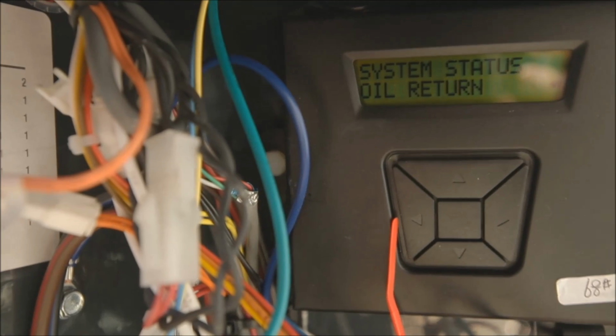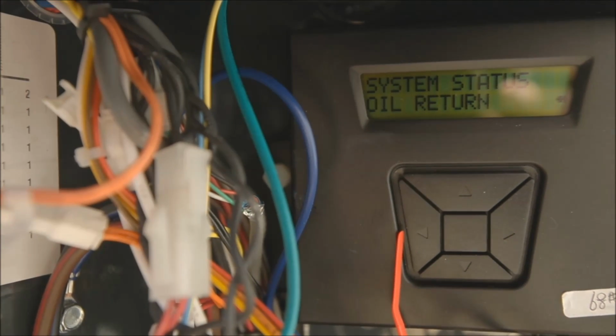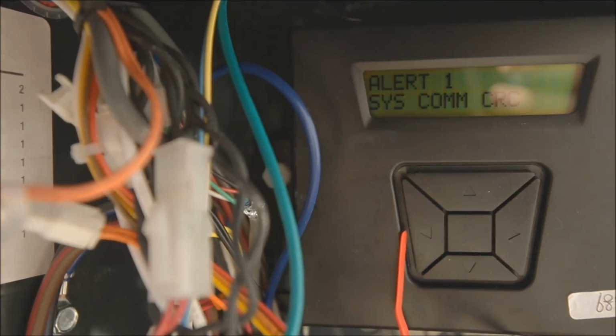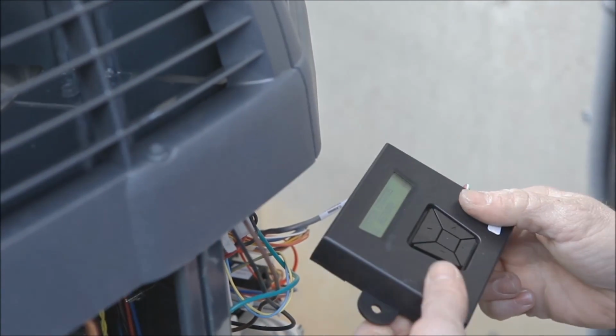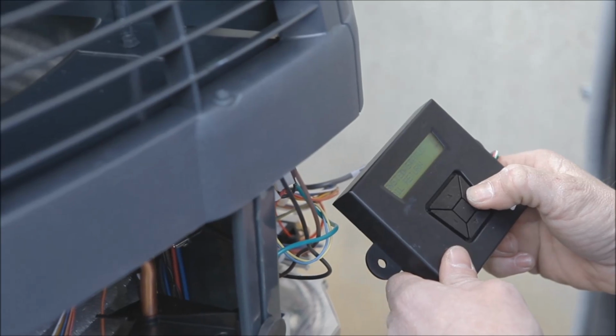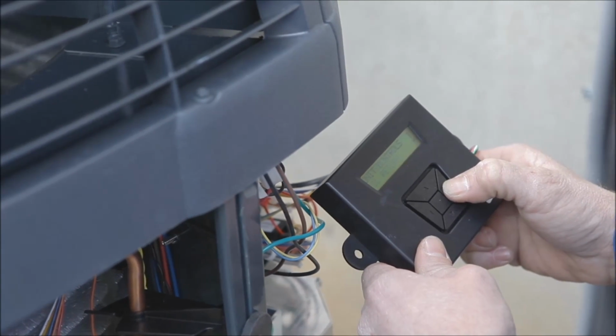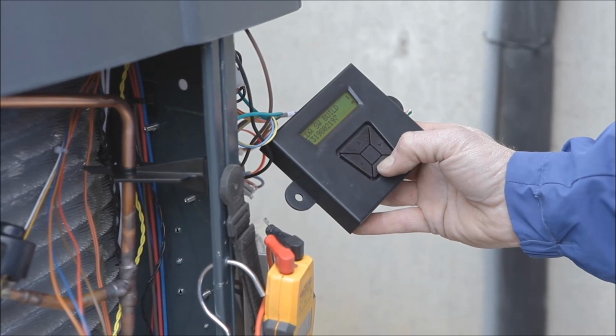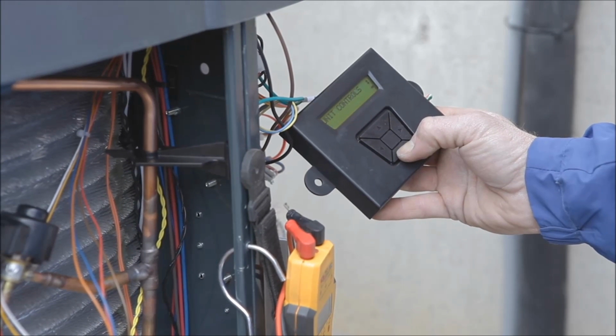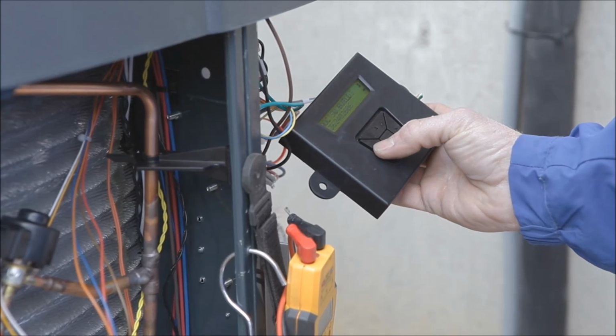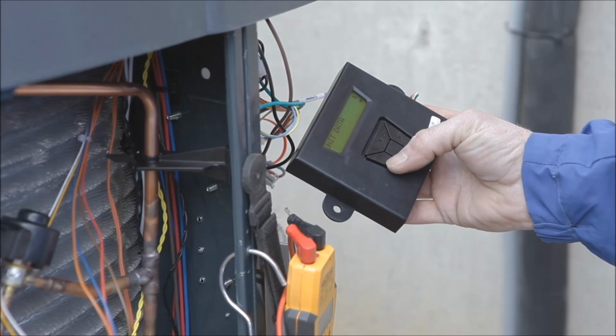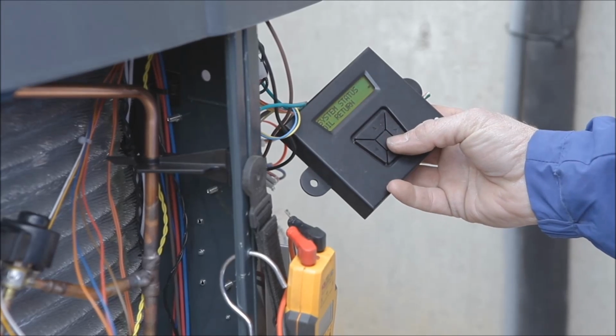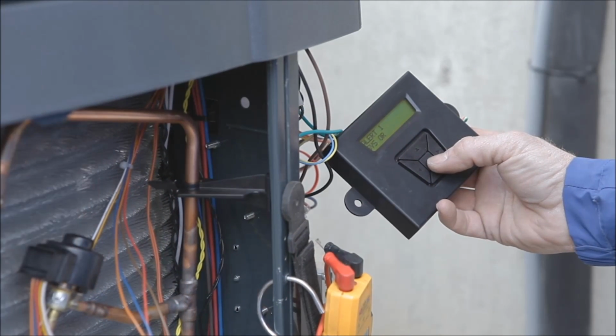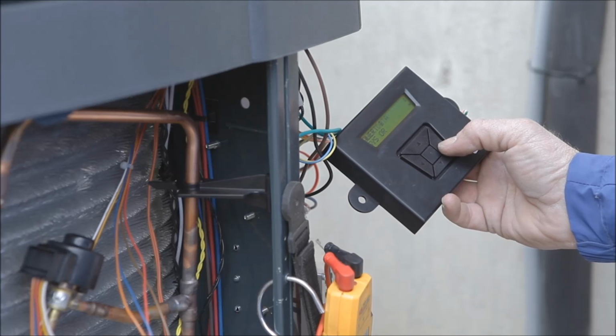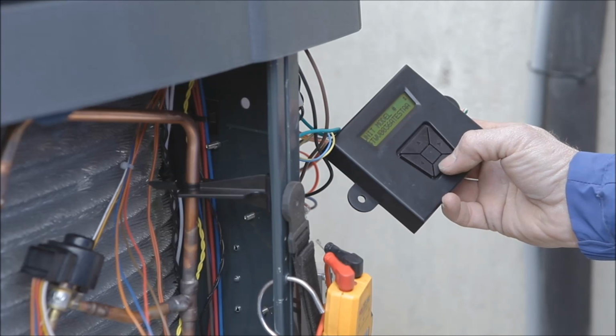All communications controlling the variable speed fan operation are displayed on the communicating display assembly. This assembly, also known as the CDA, is located at the top of the control panel of the unit. The CDA can be held in your hands for ease of programming by removing the two plastic retainer screws. After completing the required technician training, the installer will be able to scroll through the installation menu on the CDA, selecting the desired comfort options that are available for each unit's application. See the installer guide for the comfort options that are configured from the CDA in the outdoor unit.